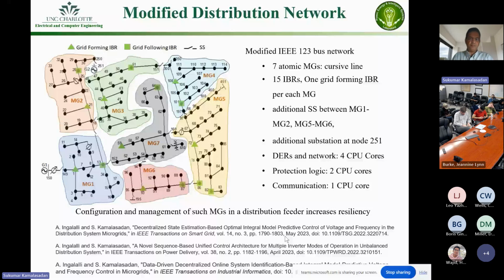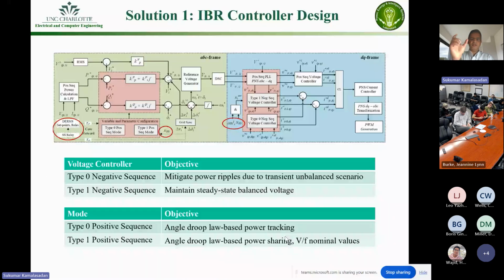So here is an example of a modified distribution network with those islands on the IEEE 123 bus system. The control architecture is a unified controller, which means it can work in the grid connected mode and in the islanded mode without having to move from one control architecture to another. It can also work on different objectives on different levels. You can see there are two types mentioned here, type 0 and type 1, which include the grid connected and islanded mode conditions.